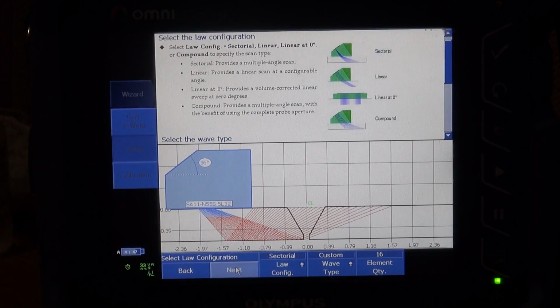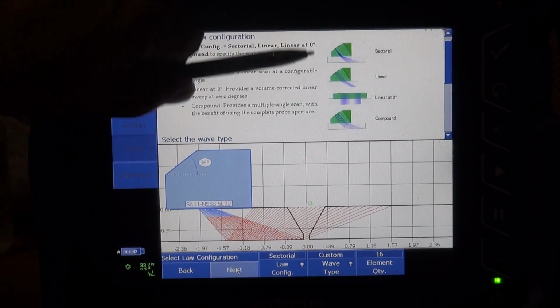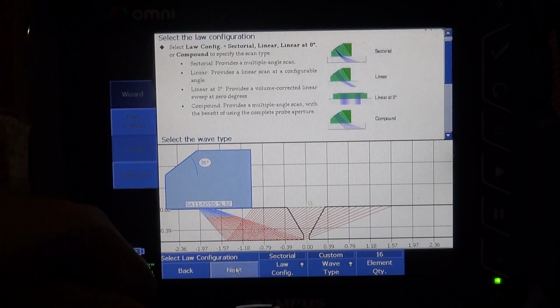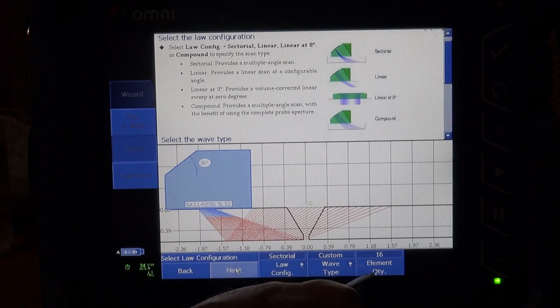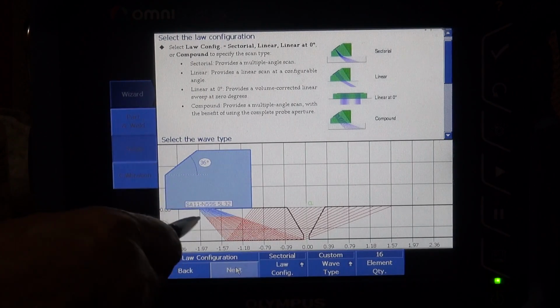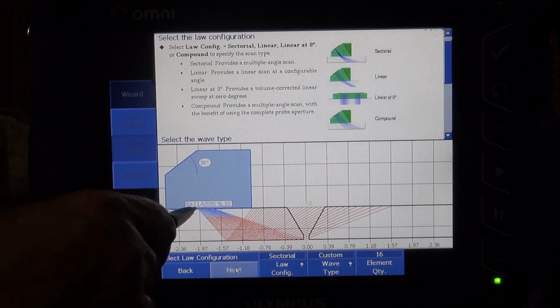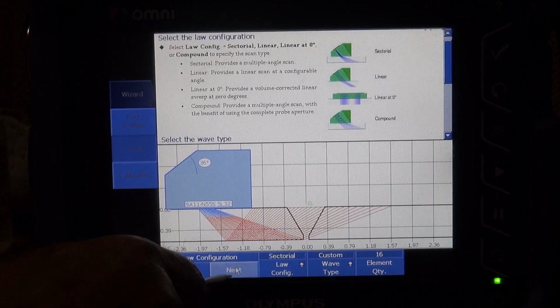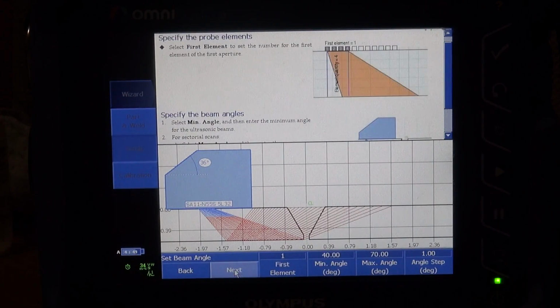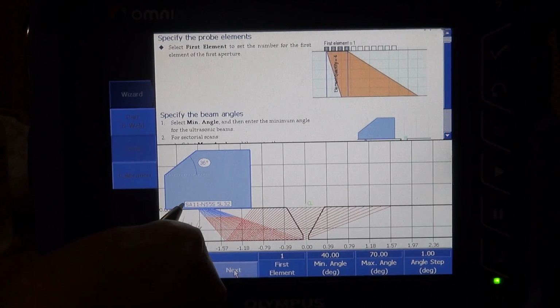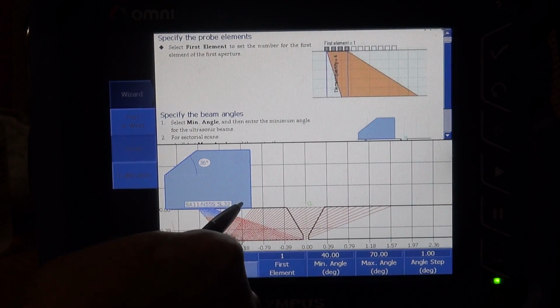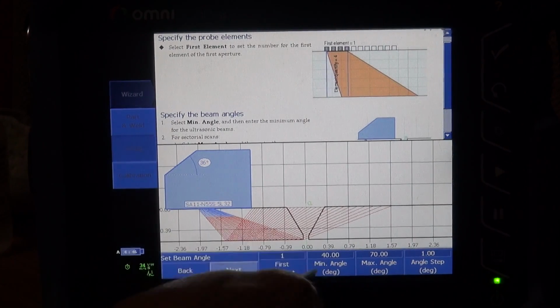It's a sectorial scan. Shows the different scans you can do. I chose a sectorial scan, and it's a 16 element of the 32 are used. I'm using 16 of the 32 elements in this transducer. Next, I'm starting with the first element. In the back is the first element all the way up to 32. I'm using the first 16.